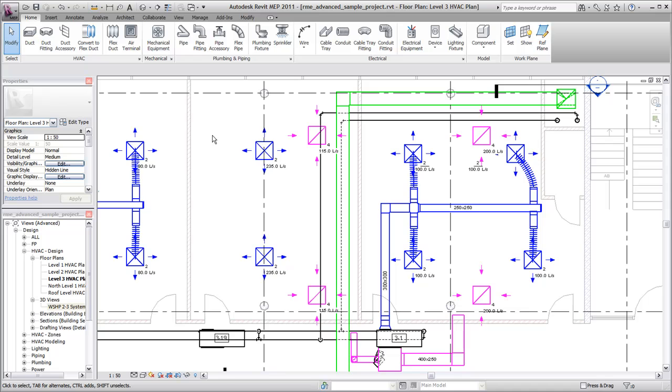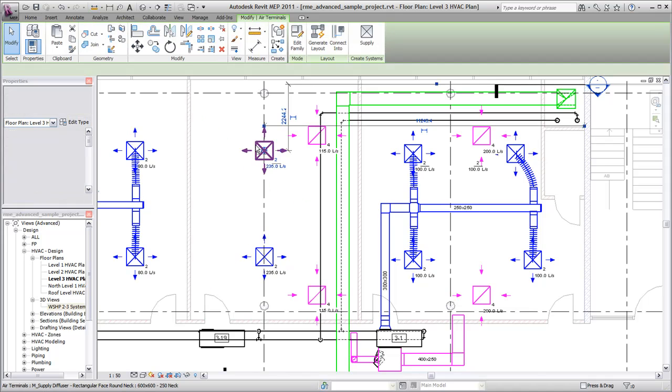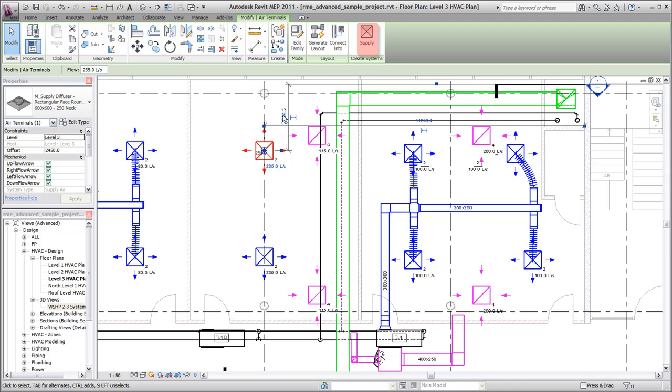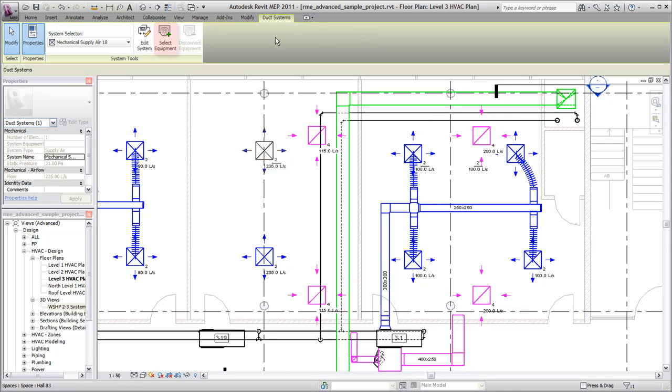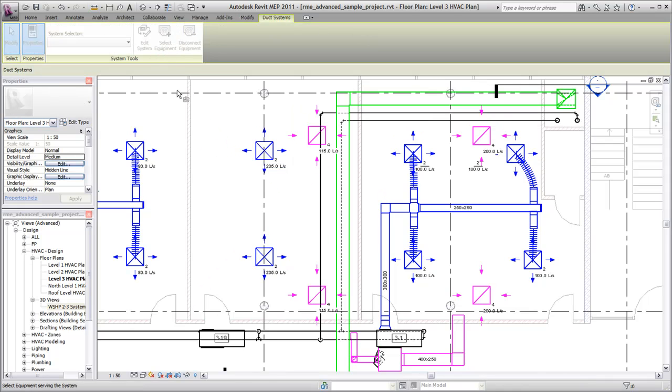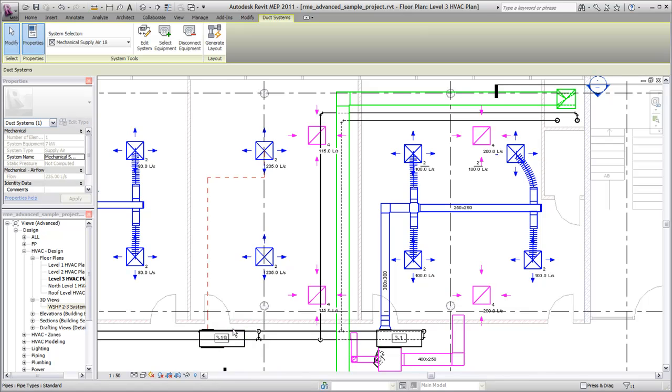Now you create the logical system by assigning the air terminals and air handling equipment to a supply system. First, select an air terminal, and then on the Modify tab, click Supply. Total flow is based on the flow for individual components in the system.